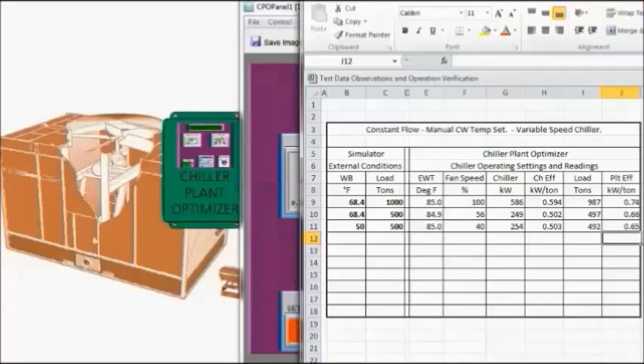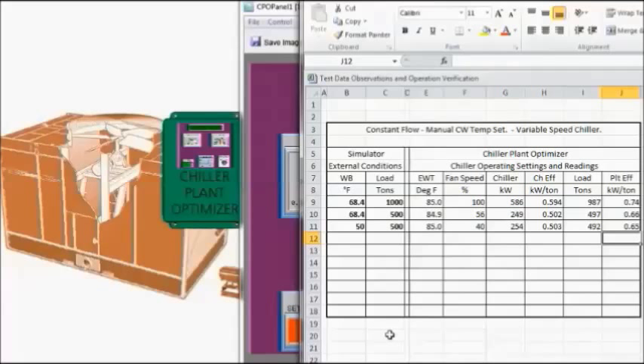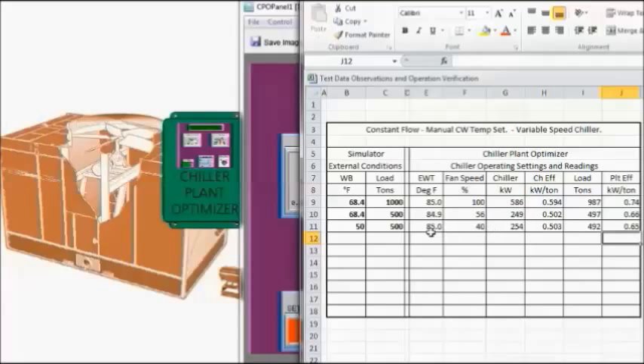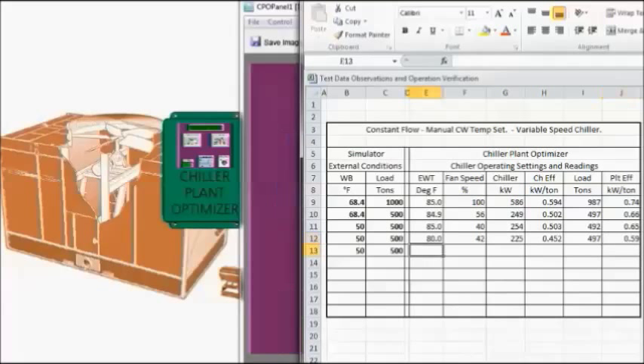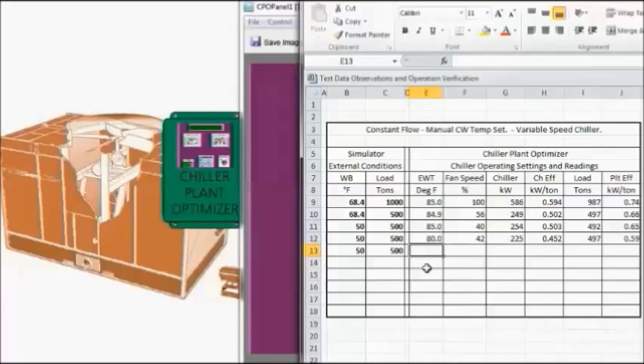Again we have not done any condenser water temperature reset at this point. We just dropped the wet bulb temperature. There's been virtually no change, maybe a small amount due to a reduction in fan speed. Now I reduced the condenser water temperature to 80 degrees and took a set of data. And now I'm going to reduce it again to 75 degrees.